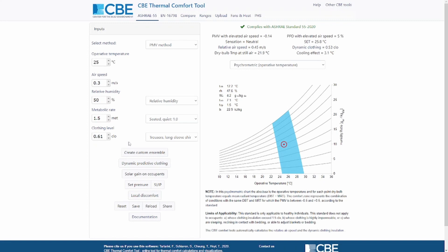The ASHRAE 55 for airspeed greater than 0.1 meters per second uses a slightly different approach from the classic PMV model developed by Fanger. As you can see, ASHRAE 55 is first calculating a cooling effect. This cooling effect is subtracted from the air temperature, and the air velocity is set to 0.1. All this is done in the back end and then the CBE thermal comfort tool uses this value to calculate the PMV value.